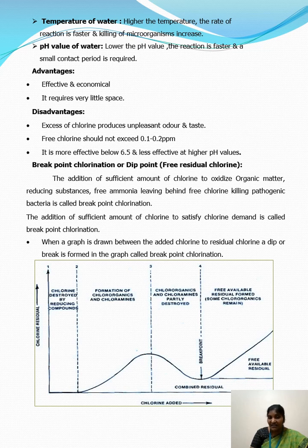Everything starts getting reduced. First we initially had reduction, and now we will have the oxidation process. All the chloramines that were originally formed now start getting oxidized. They get destroyed, and this is shown as the dip in the curve. The last dip in the curve, you can see the pointer there. I'm showing you the pointer here.